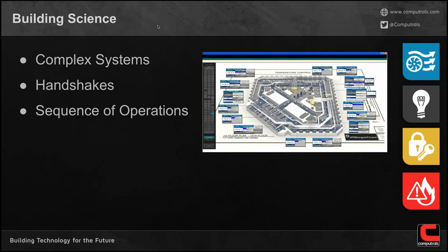Another event that may take place as a result of that smoke detector detecting smoke is the recalling of elevators. When there's a fire or smoke condition in a building, it's preferred that you do not use elevators, so they close their doors and recall to their floor of egress and remain there. The voice evacuation system will notify building occupants to use the stairwell as an evacuation rather than the elevators. These are all independent systems that work in unison to achieve different tasks during this single event.